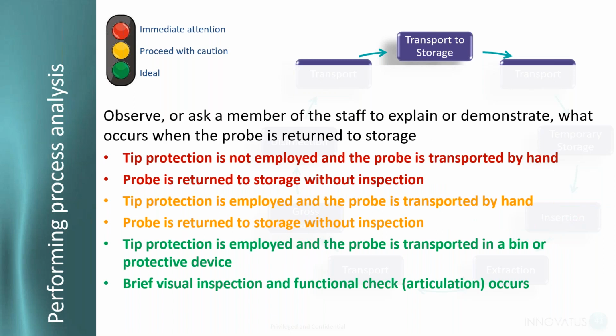So again, we're going back to storage. We've disinfected the probe and we're transporting it back to our storage area. You're starting to see a pattern here. If tip protection is not employed and we're transporting it by hand, not a good idea. If we return to storage without inspection, not a good idea. Ideally, we want tip protection employed and we want it transported in a protective bin. And then we also want to do a brief inspection and functional check or articulation check before we put it into storage.